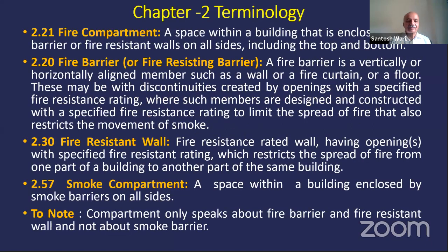So we will go through the definition first. The compartmentation is a space within the building which is covered with fire barrier or fire resistance walls on all sides, including the flooring and the ceiling. This is the definition of compartmentation as per the terminologies given in 2.21 of Part 4 of National Building Code 2016. Then the fire barriers. The fire barrier is a vertical or horizontal aligned member such as a wall or fire curtain or a floor. This may be discontinued after certain openings, with a specified fire resistance rating. This fire resistance rating is very important. Such members are designed and constructed with the specified fire resistance rating to limit the spread of fire and also restrict the movement of smoke.